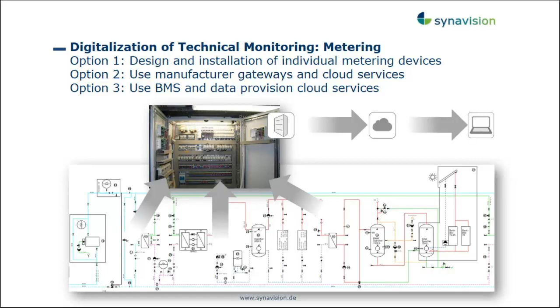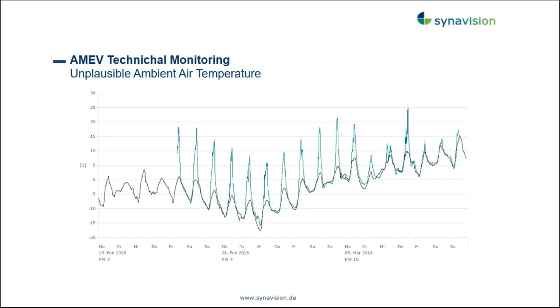Once you have that in place, you can see a lot of typical problems of buildings right before you actually hand over the building, before you sign the final acceptance documents. For example, here's an example from one of our projects: a very implausible ambient air temperature. There was a sensor on the roof that was not protected from sunlight. The black temperature here was the real temperature - this is what the BACS system actually measured. And of course this messed up the whole control system.